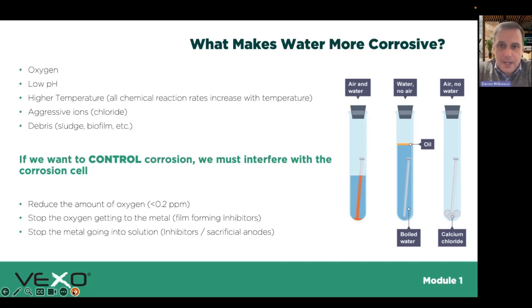Higher temperatures, again, corrosion rates and chemical reaction rates increase with temperature. So it's typically why you'll see a lot more of this magnetite in a heating system than you would on a chilled water system. We can have aggressive ions within the water, for example, chloride. That can create stress corrosion cracking, for example, on stainless steel. If it's highly concentrated, certainly locally, we can see failure.